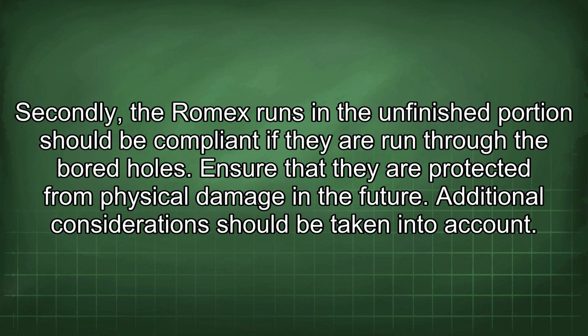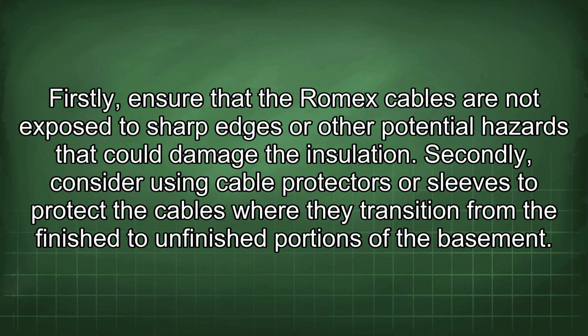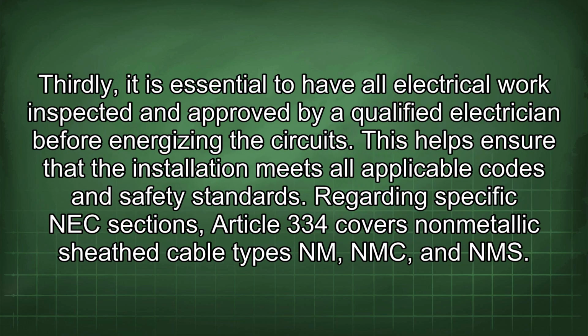Additional considerations should be taken into account. Firstly, ensure that the Romex cables are not exposed to sharp edges or other potential hazards that could damage the insulation. Secondly, consider using cable protectors or sleeves to protect the cables where they transition from the finished to unfinished portions of the basement. Thirdly, it is essential to have all electrical work inspected and approved by a qualified electrician before energizing the circuits. This helps ensure that the installation meets all applicable codes and safety standards.